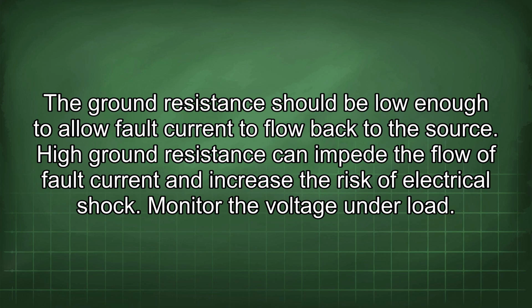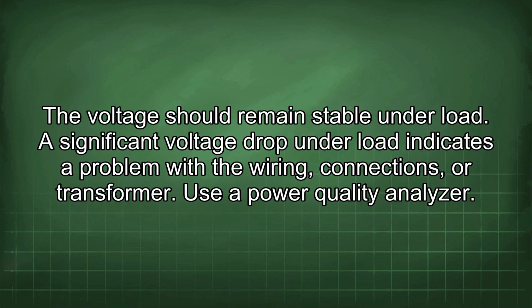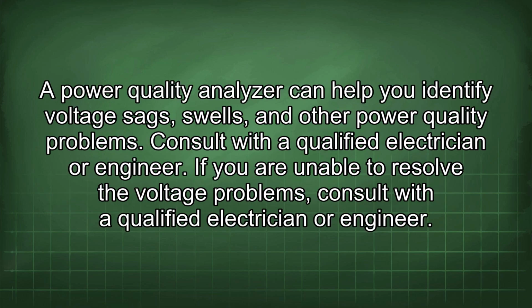Monitor the voltage under load. The voltage should remain stable under load. A significant voltage drop under load indicates a problem with the wiring, connections, or transformer. Use a power quality analyzer. A power quality analyzer can help you identify voltage sags, swells, and other power quality problems.